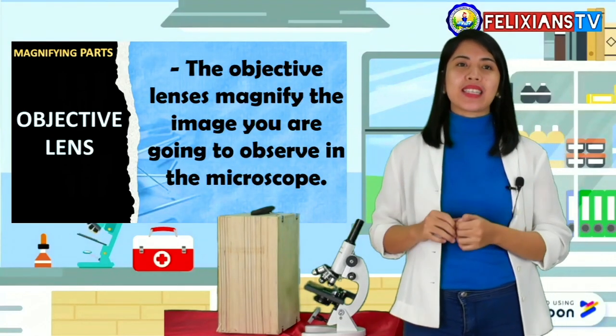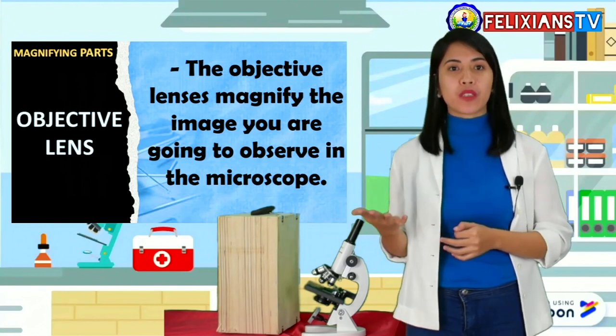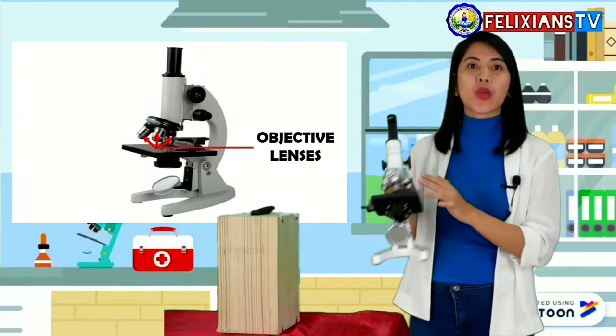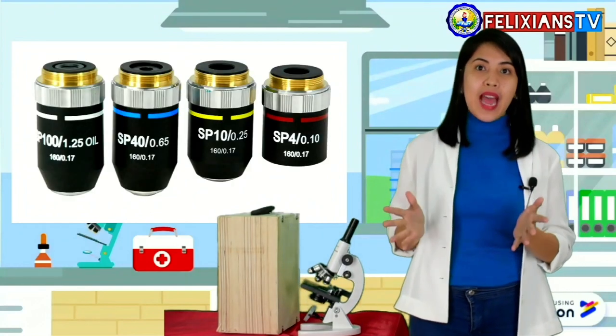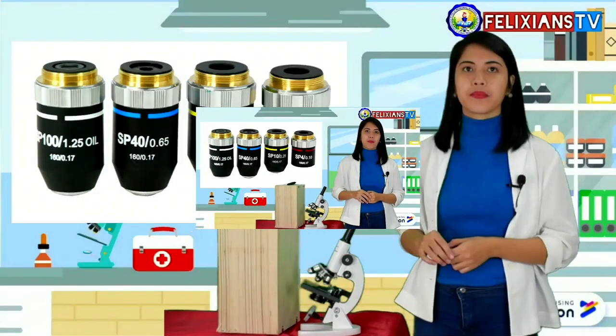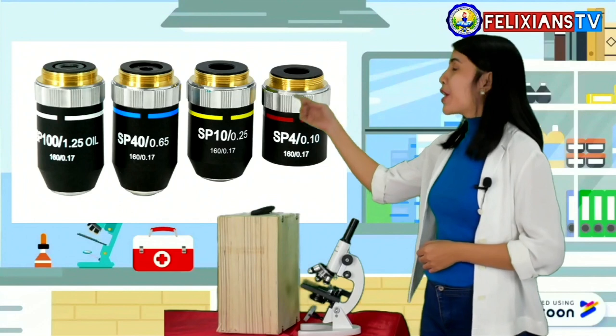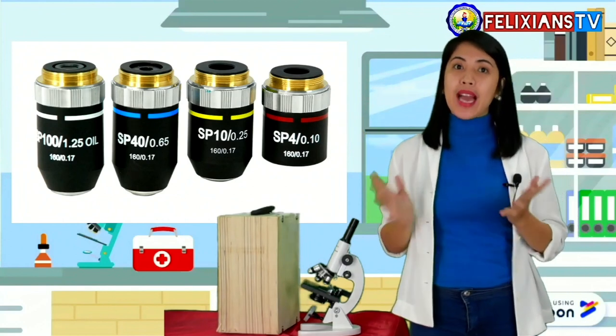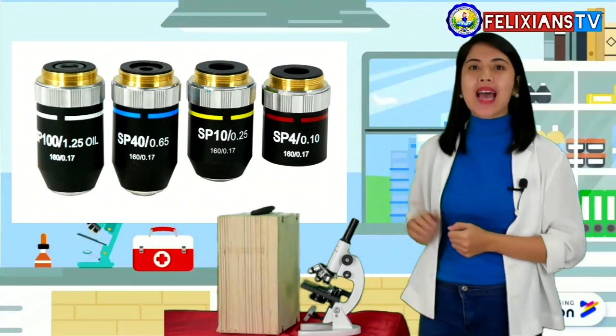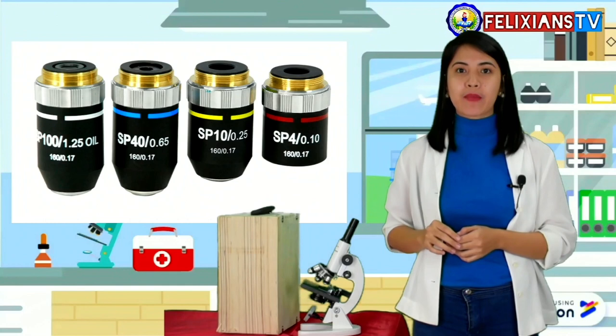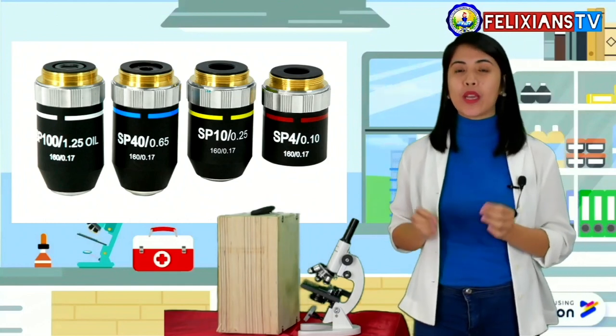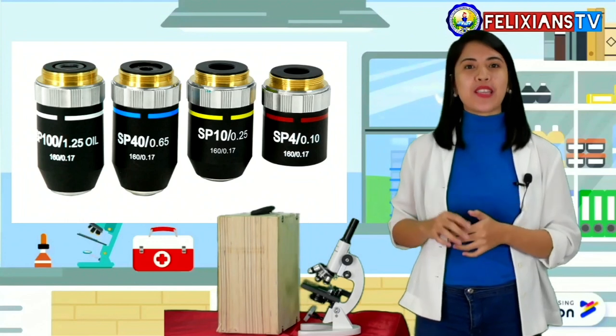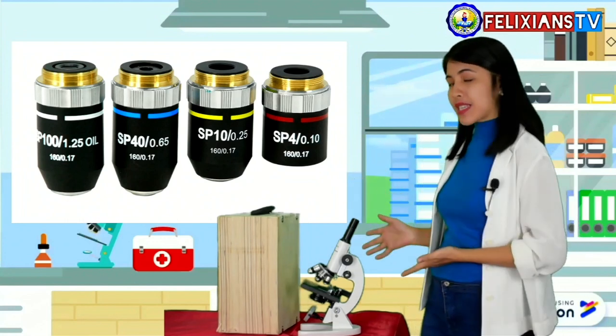Next, the objective lenses. The objective lenses magnify the image you are going to observe in the microscope. So, these are the objective lenses. The objective lenses also have their corresponding number of magnifications, but each lens has different magnifications. The red one is the scanner, which is four times. The yellow one is the low power objective or the LPO, which is ten times. The blue one is the high power objective or the HPO, which is 40 times. And the white one is the oil immersion objective or the OIO, which is 100 times and is used to observe bacteria. So, different microscopes have different magnifications.